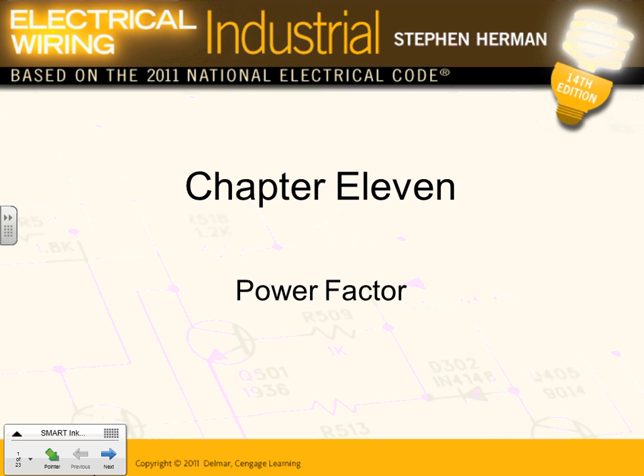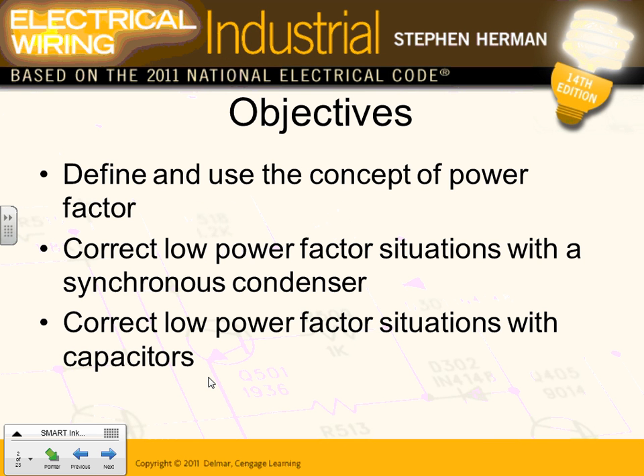Okay, so let's go ahead and talk about this magical power factor. We want to talk about the concept of power factor, guys, why power factor is important, and the situation with correcting it. We'll talk about what a power factor is first, and then how you correct it. You correct the power factor in two ways, either by adding big fat hamburgers. Anybody knows what a hamburger is in terms of beef and bun? Yeah, but instead of having that one, beef and bun, you have a capacitor. I call it hamburgers. You add basically hamburgers into your system, a capacitor, right? That's what a capacitor is, beef and bun. Or you can have a synchronous motor, synchronous condenser or motor that also can correct your power factor. We'll talk about this one in a second.